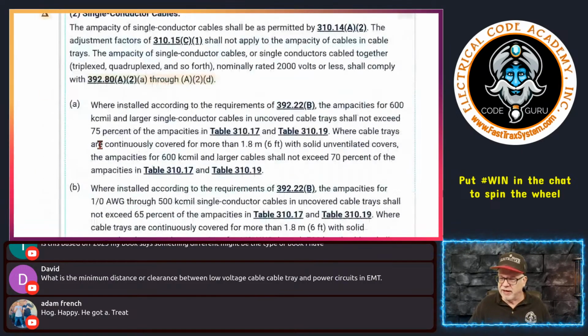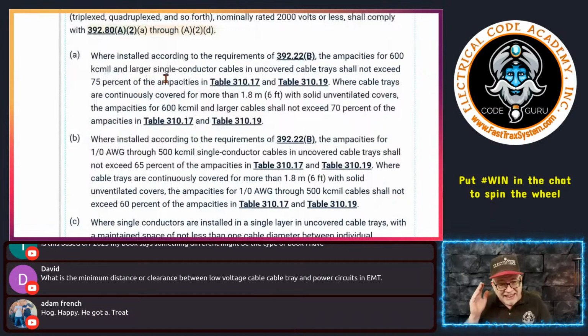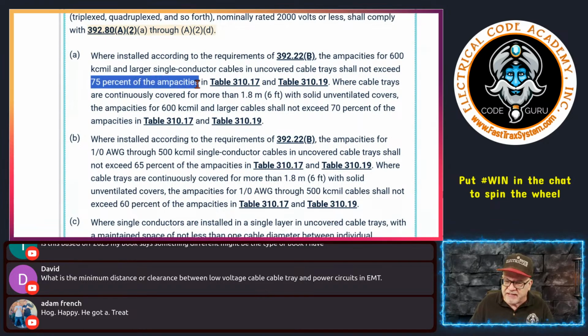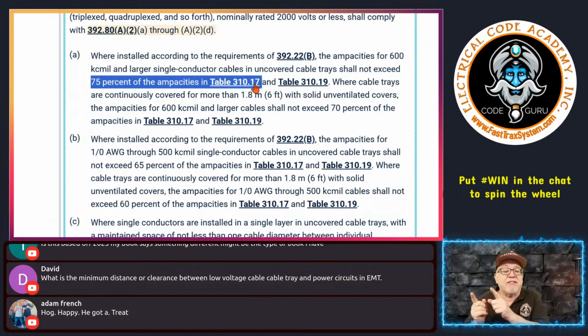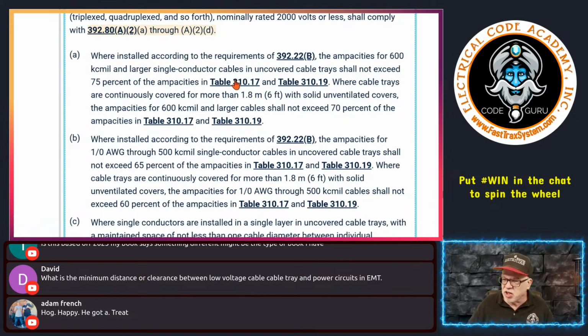Okay, so there we go. What you're going to do is take that value under 310.17 and reduce it to 75% of that value. And I don't know how that equates to 310.16. That'd be a fun little thing for folks to do. Say, look, if I just use 310.16, which you can't go wrong with, what's the ampacity of this conductor? But what is it at 75% of the value in Table 310.17? Okay, that type of thing. All right, so there you go.